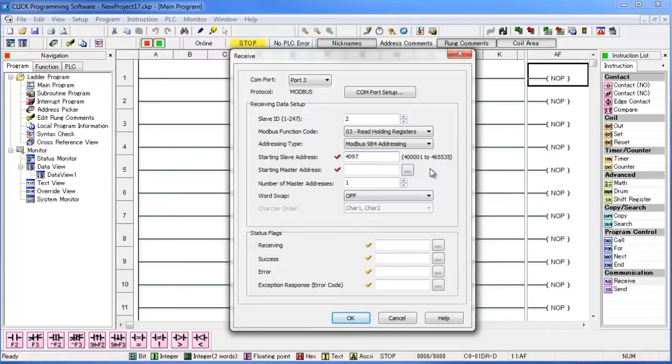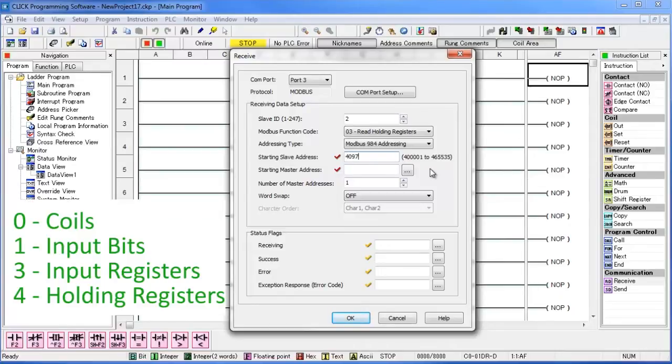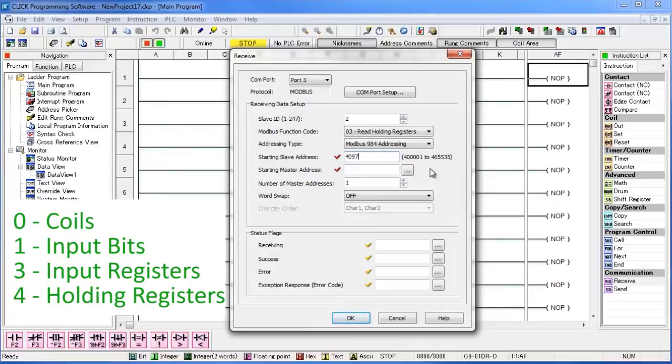With Modbus addressing, we must include a function code at the beginning of the request. The function code relates to a certain register type. A 0 relates to coils. A 1 relates to input bits. A 3 relates to input registers. And a 4 relates to holding registers.